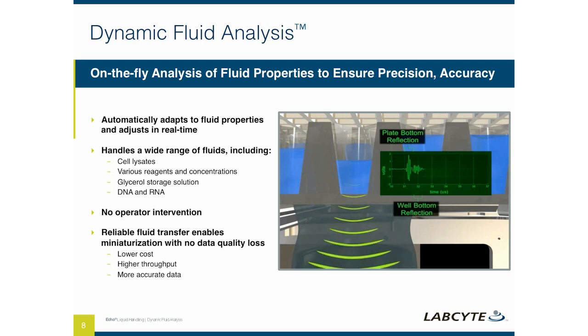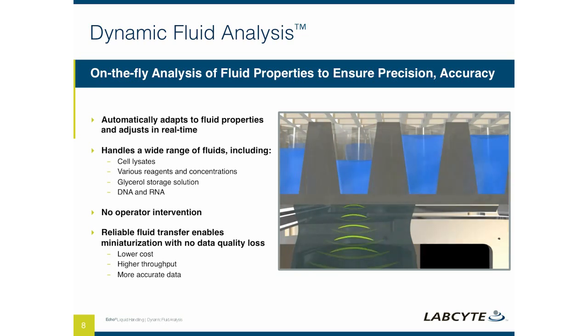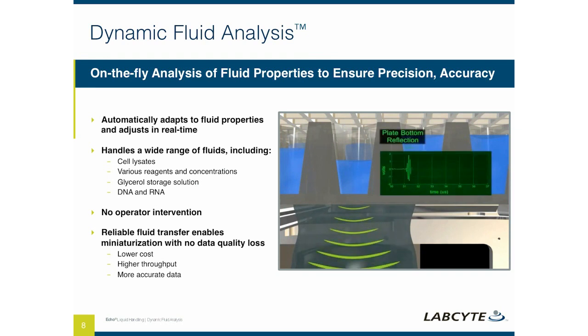When you set up the experiment, you're going to define a specific fluid class, and those are very general. It's going to be buffer or buffer with surfactant, or buffer with glycerol, for example, or DMSO. Very broad range fluid classes, and then the instrument will use this dynamic fluid analysis to determine the other characteristics necessary to ensure that the droplets being ejected are of the correct volume and are highly precise.